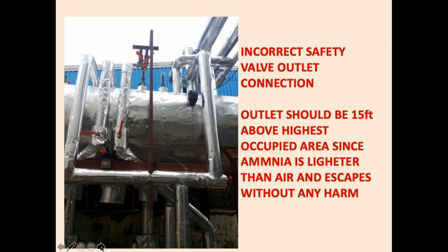The next slide shows an installation I saw just about 6 months back in Mumbai. They have used dual safety valves, everything okay, but in order that it should not go to the occupied area, instead of taking it 15 feet high, they have taken the pipe down into the machine room. The whole purpose of the safety valve is defeated, because if it blows off, the entire ammonia will go to the bottom, into the occupied area. So this is totally incorrect piping, and the logic was totally incorrect. We had to modify this.